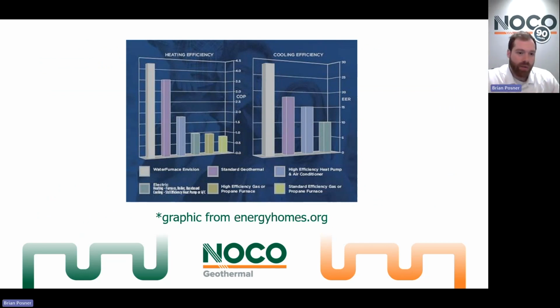So to show that in chart form, you have a heating and cooling graph here showing the efficiencies of different systems based on their coefficient of performance. You can see a high efficiency gas or propane furnace is going to be on the bottom right side of the heating efficiency chart. You can see those coefficients of performance for electric, high efficiency gas or propane, and standard efficiency. Those are all up to or just limited at 1. For all of those, you can't get more heat than what you're combusting, burning, or running through resistance.